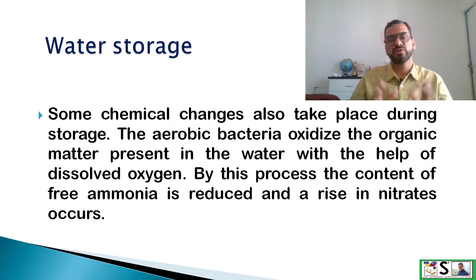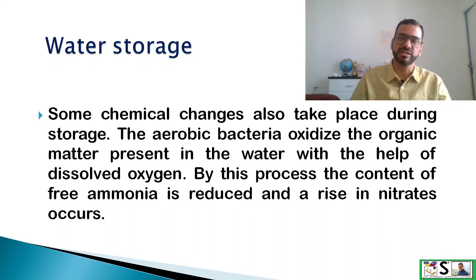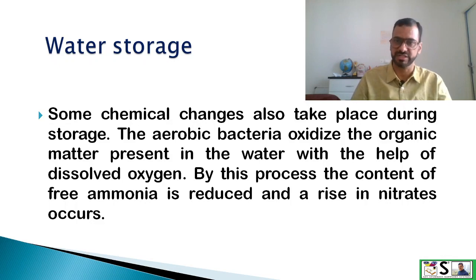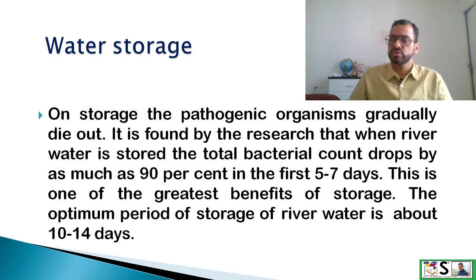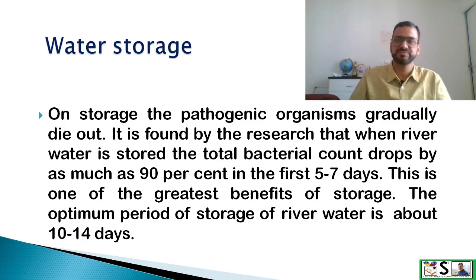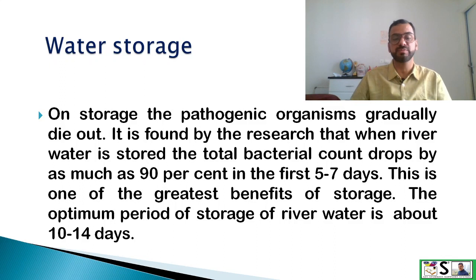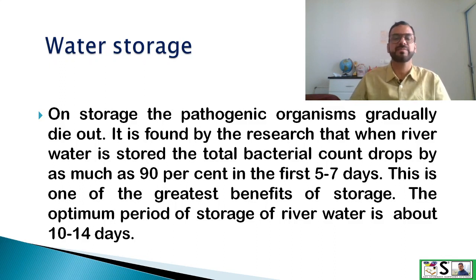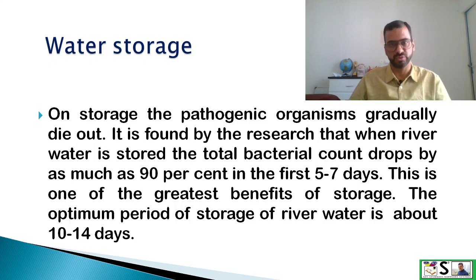Sometimes an aeration process is also added in some water treatment plants to introduce oxygen into the water. On storage, pathogenic organisms gradually die out. Research shows that when river water is stored, the total bacteria count drops by as much as 90% in the first five to seven days. The optimum period for storage is about 10 to 14 days.